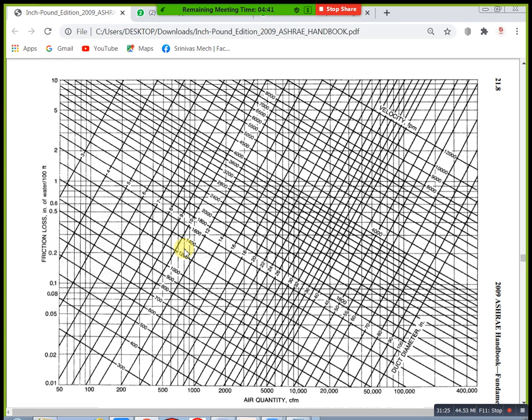1300 fpm. Now you can compare with your maximum velocity. This is less than the maximum velocity, meaning it is applicable for this method. Now this condition is accepted. Next, again you take 5000 and 0.08, both are matching here.